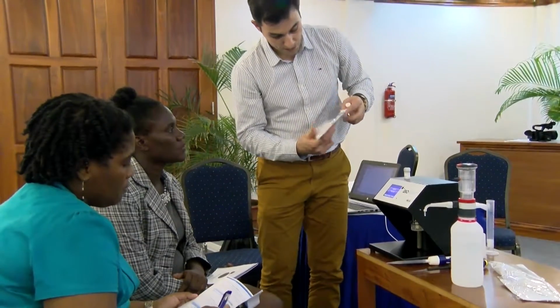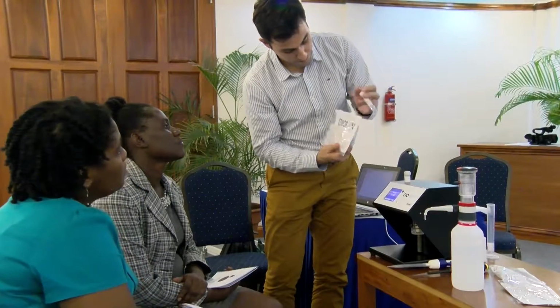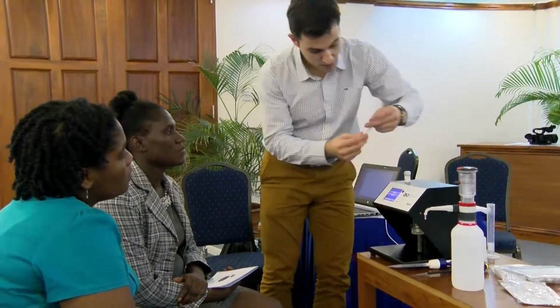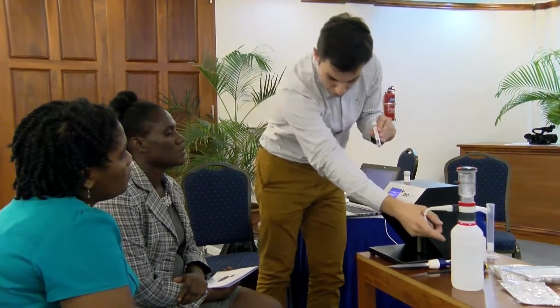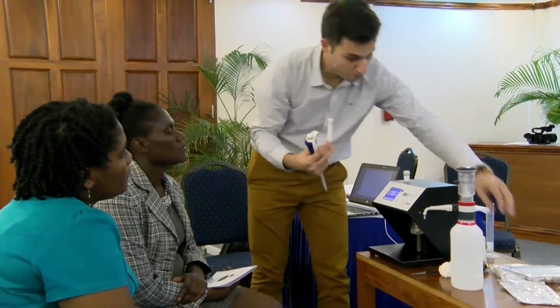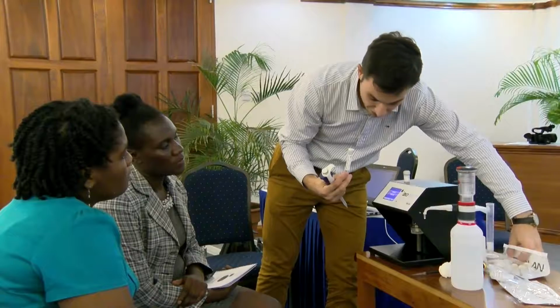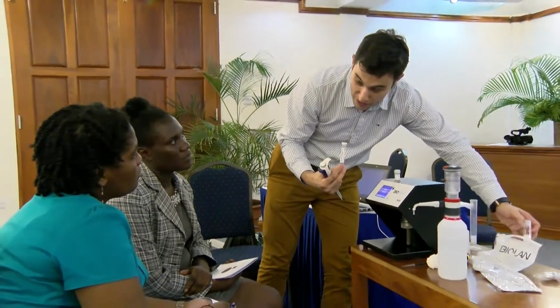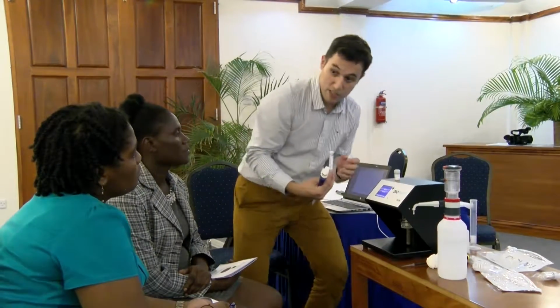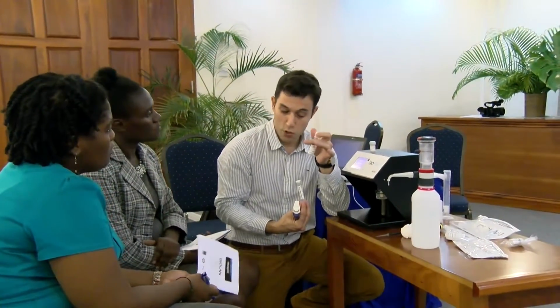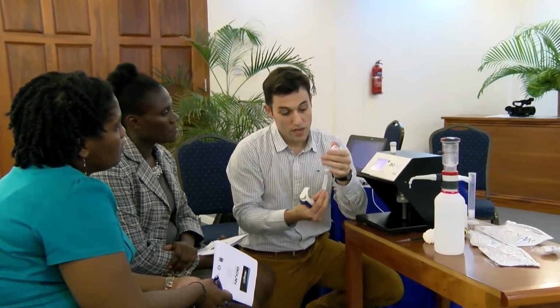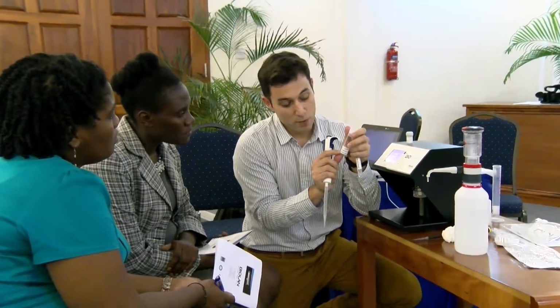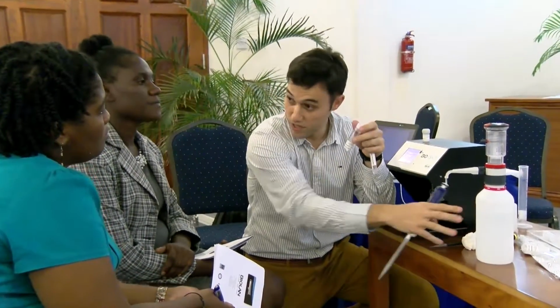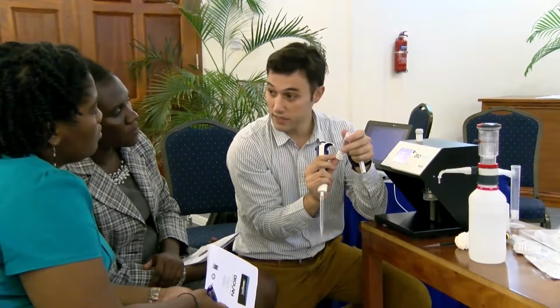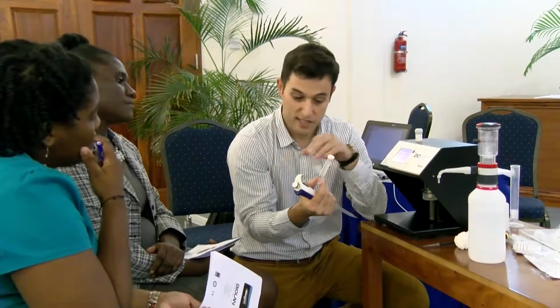I have here one of these tubes already prepared. I prepared it before. This is already hydrated with 10 milliliters of measurement solution. With this calibration reagent, which we can call the calibration reagent mother, we prepare the calibration standard, the son. It is needed to prepare it every day. It's very simple. We have to just add 19.9 milliliters of, again, measurement solution, and 100 microliters of the calibration reagent, nothing else.